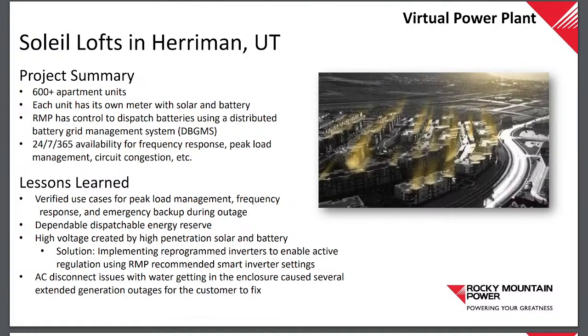So we have used it for frequency response. There was an outage last year on that circuit where we verified that if it weren't for those batteries and their microgrid, they would have been out of service. But they did have that ride-through, and they verified that they remained in power. So that was a good case there.